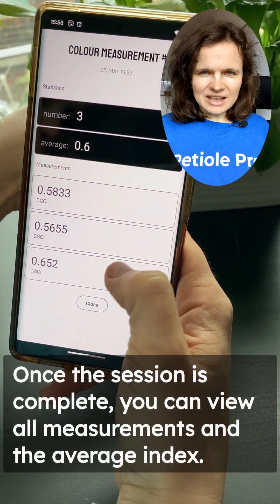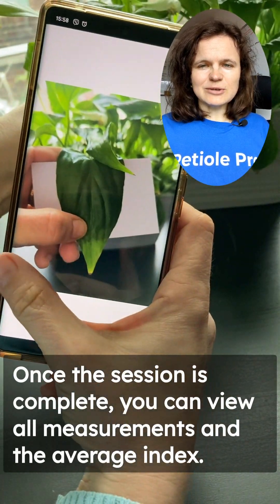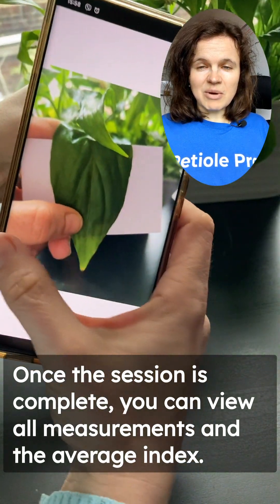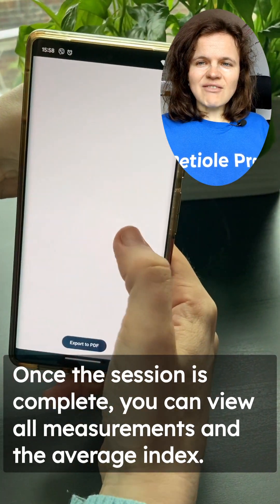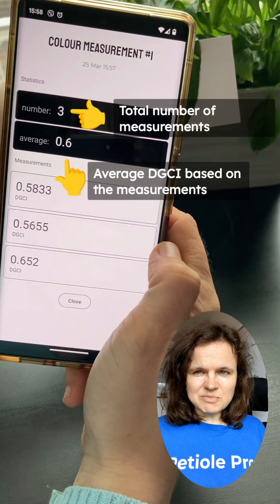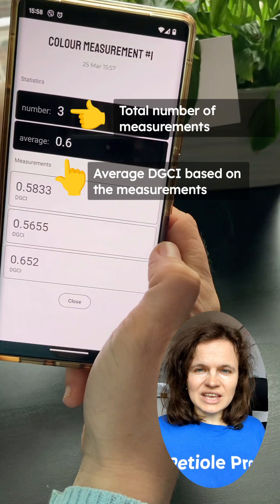Once you have taken all your measurements, the Petiole Pro will display the total number of measurements — in our case it's 3 — and the average DGCI value. You can also access each individual measurement and see the value of each DGCI measurement during the session.